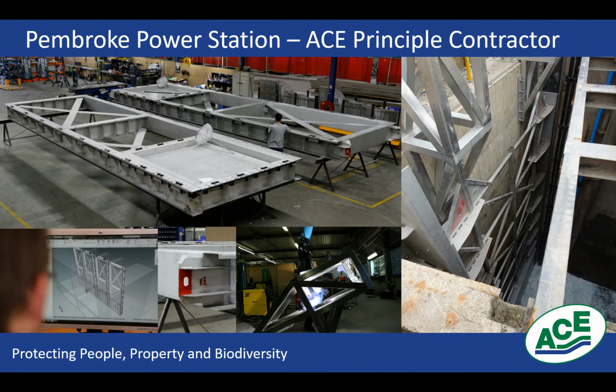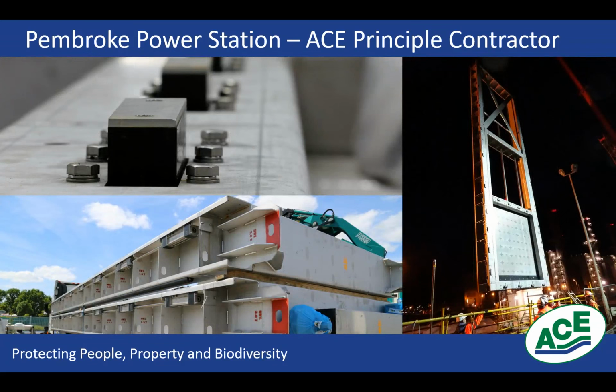from a capital perspective. We noticed on site that there were some rebates, and these rebates were used for stop logs. Now, looking at the rebates, we could see, wait a minute, that's something we could potentially put the penstocks in. That would prevent all of the sheet piling, that would prevent all of that dewatering activity if we could just lower them in. But we do need to come up with a solution to actually jack them in place. So we created these jacking bolts, which you can see here, and they were connected by a spindle. So each one's a gearbox with a spindle running through. So as you turn the spindle, these jacking bolts wedge out.